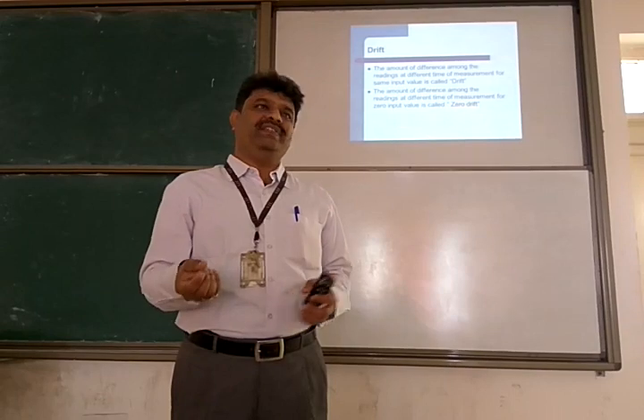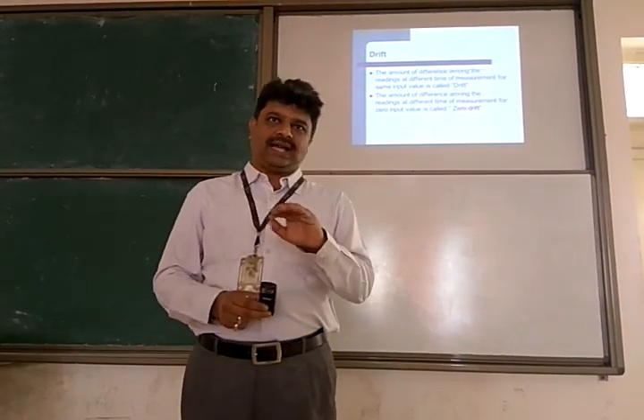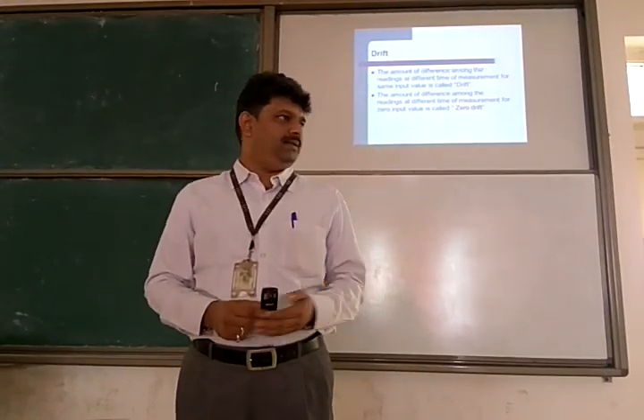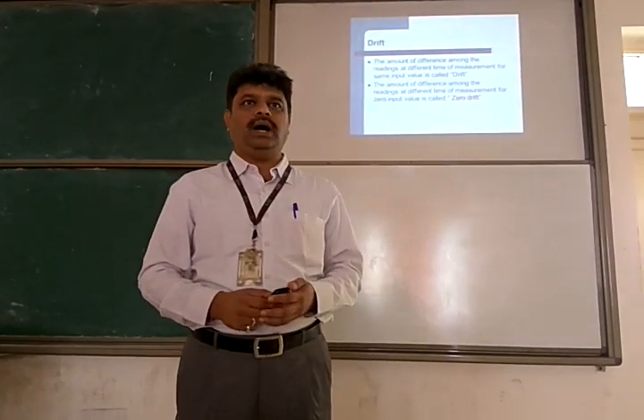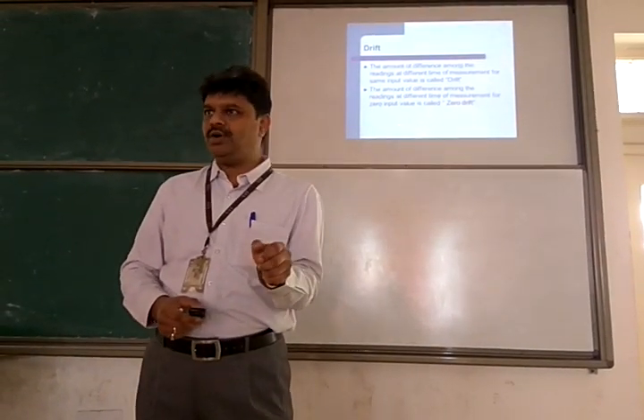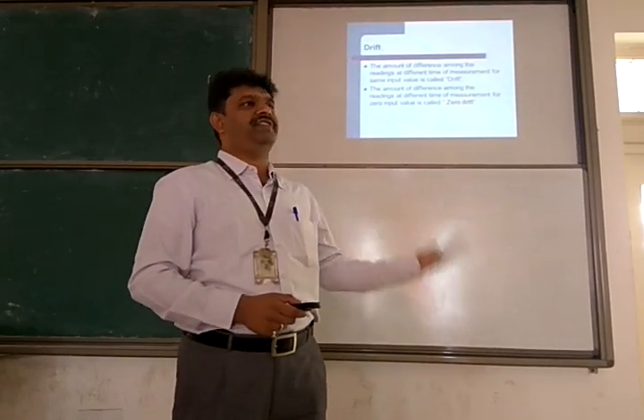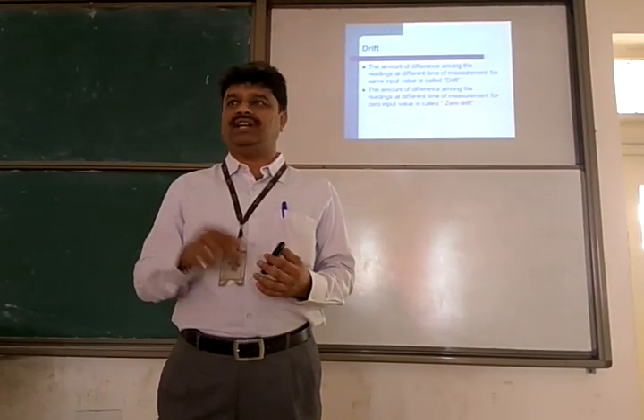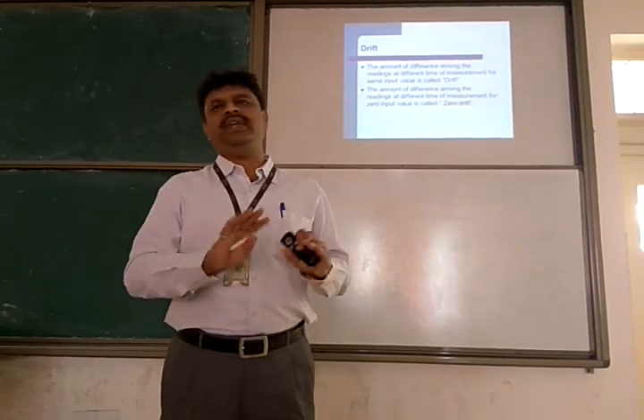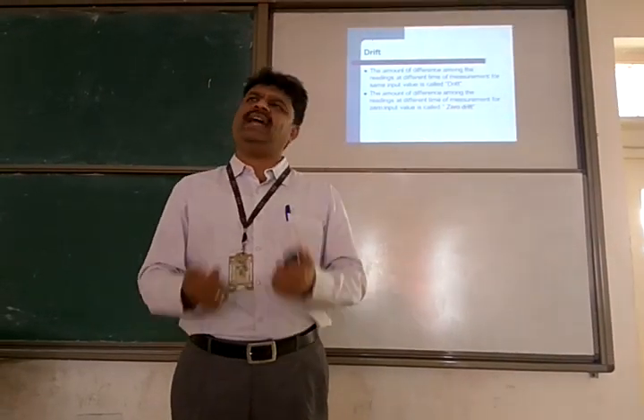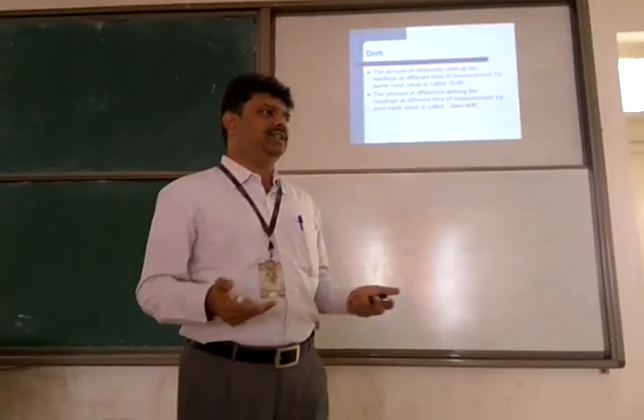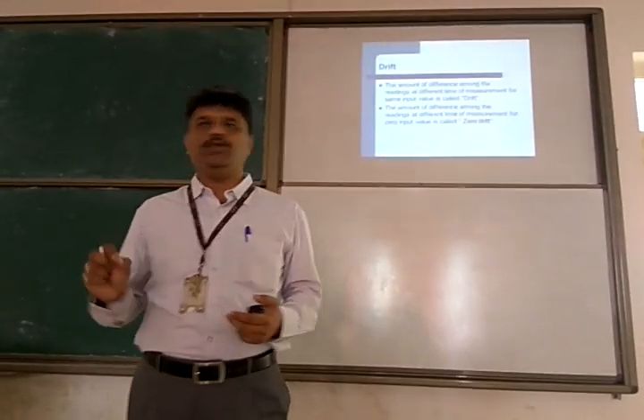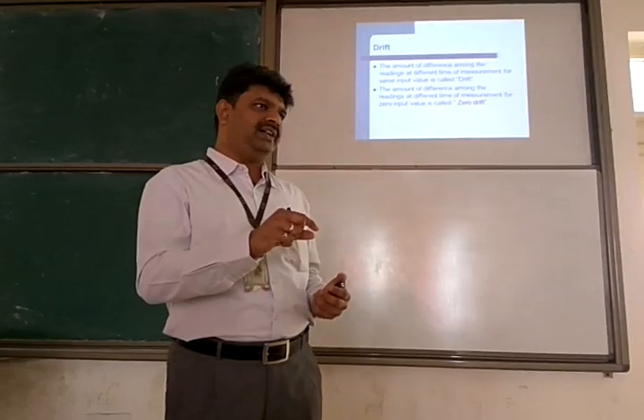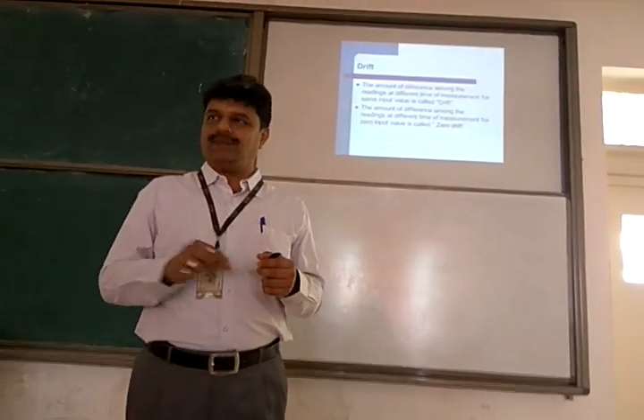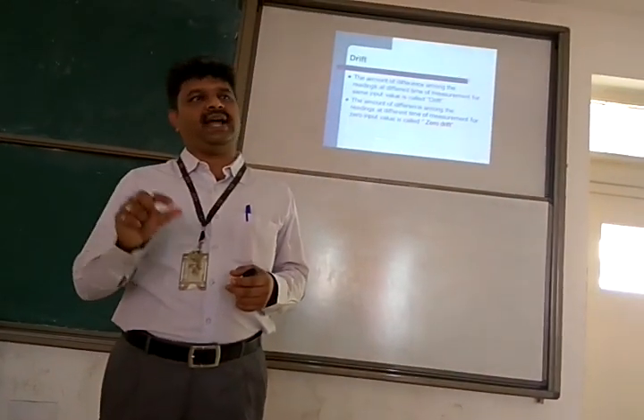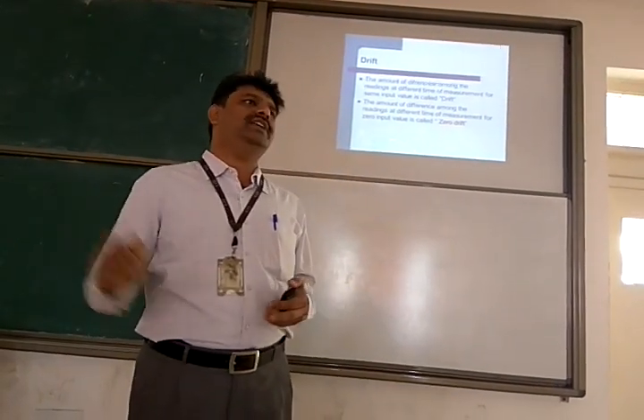If it is an electronic instrument, zero drift can be adjusted; the zero setting can be done. Yesterday in the lab, some of the instruments you might have adjusted to 0. That is because you are adjusting the zero drift, nullifying it. Then your measurement is good. But if it is a mechanical instrument, it is not all that easy. You may have to correct it manually. You compute the drift, keep it in memory, and while taking a reading you subtract or add accordingly so that you get the correct measurement.